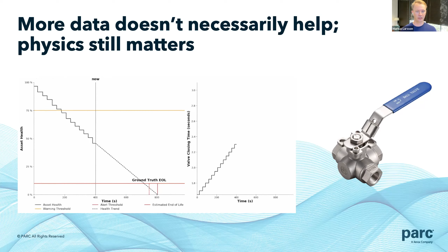So what's the takeaway? Most control systems we've come across have sensors that detect whether a valve is open or closed at around 1 hertz or even 0.5 hertz - once a second or once every other second. Given how even subtle changes in valve closing time impact asset health and ultimately operation, if all you can pick up is a step change of 1 or 2 seconds, it really won't be very useful for predicting when to shut down and flush or clean out a valve in this case.